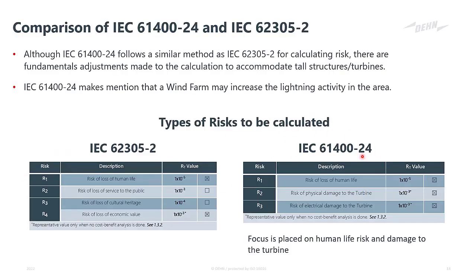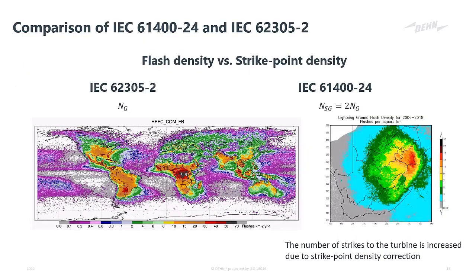In 61400-24, we calculate loss of human life, similar to 62305. But we split the risk of economic loss. So we calculate the risk of physical damage to the turbine and the risk of electrical damage to the turbine. So this is a fundamental difference between the two. There's no mention of anything like service to the public or loss of cultural heritage in this standard. Now, I mentioned that the standard also adjusts the amounts of lightning strikes or the lightning activity within the area. We mentioned that it increases it.